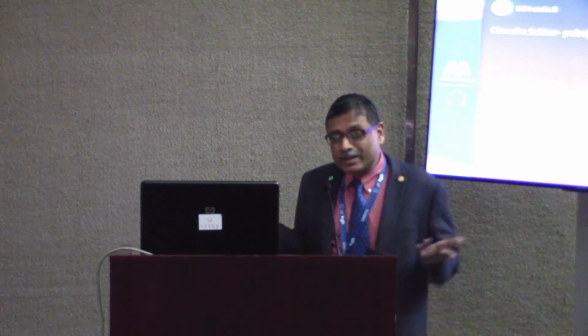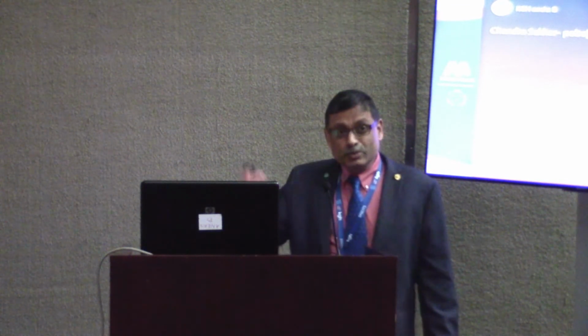In fact, there's probably no impact in terms of the humidity level inside the building, because if the levels do rise, which it will, we can probably accomplish comfort in a slightly different way. And I'll come to that as part of another strategy as we go along. The next one that I would like to just very briefly mention to you here is what we call an adaptable coil approach. Conventional cooling coils in an air handling unit, let's say we're talking about a 6-row deep cooling coil that gets, say, chill water supply temperature, what I told you earlier, 6 to 7 degrees Celsius with a delta T of similar number, 7 degrees delta T.